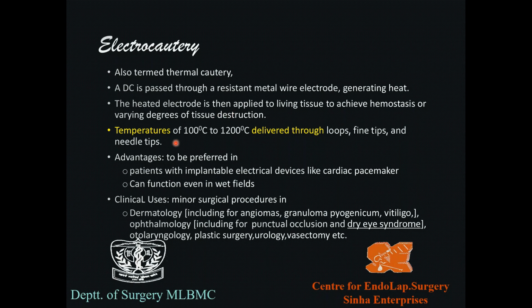Okay, now temperatures of 100 to 1200 degrees centigrade can be delivered through loops, fine tips and needle tips. So these are the probes which can be used for passing on the heat to the body. You can use a loop, you can use a fine tip, or you can use a needle tip. Now, what are the advantages to be preferred in those patients where electrosurgery may be slightly problematic? Like, for example, a patient who has an implantable electrical device like a cardiac pacemaker, or the patient has got a wet field. We all know that the electrosurgical unit that we commonly use cannot work whenever there is a wet field. We have to dry the field, only then the current passes into the body.